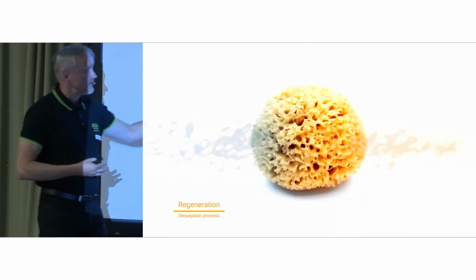This means the zeolites, the molecular sieve, can be regenerated after filling all those pores with water molecules, after saturation. So every adsorption dryer consists of an adsorption or drying process, then stop drying, and backwards regeneration. This process can be repeated many times. Many adsorption dryer manufacturers say it's about 8,000 to 10,000 hours, and then you need to replace that molecular sieve.